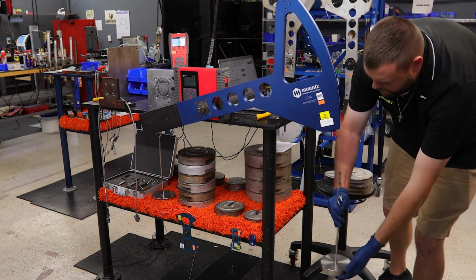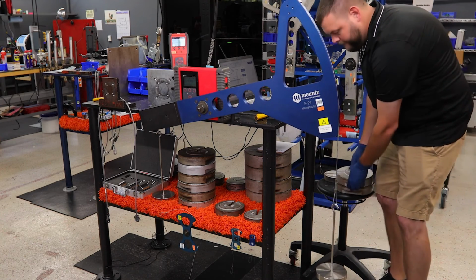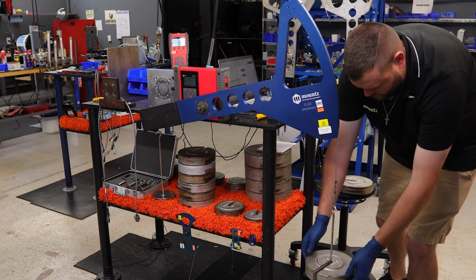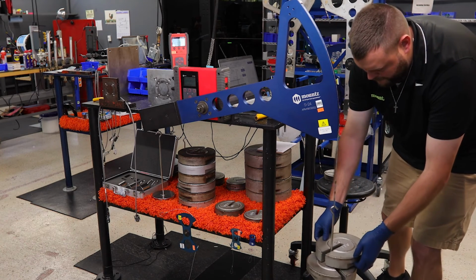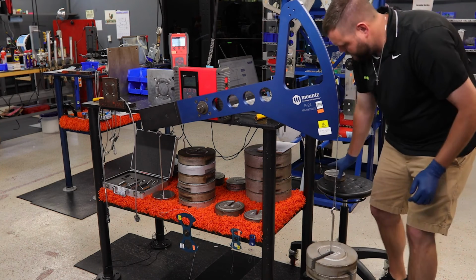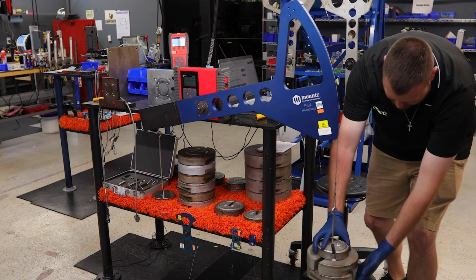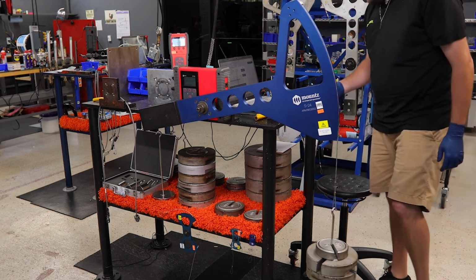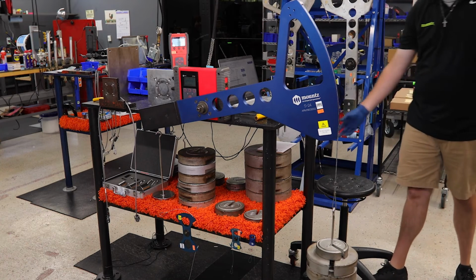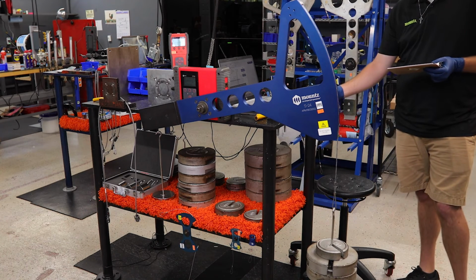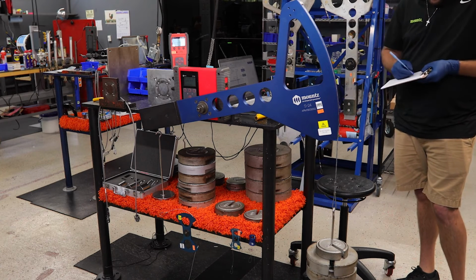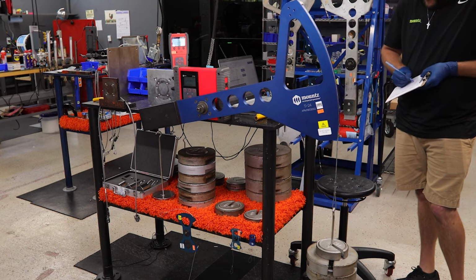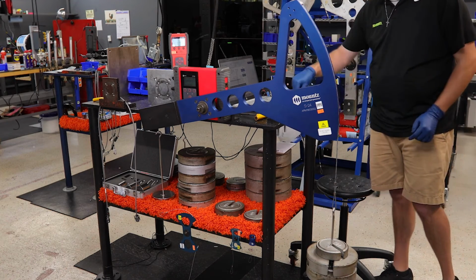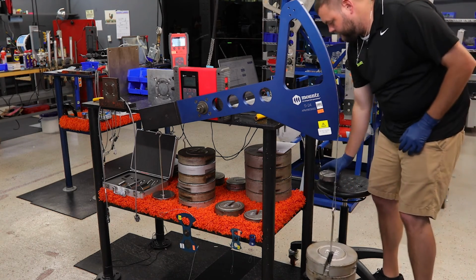And then this process is completed in the counterclockwise method, the same value or same readings at 10, 50, and 100. And then after that has been completed, the calibration data, as I mentioned, will go to the ARC2 chip where it will be stored there. And then the process will be validated to make sure that the sensor is reading correctly with that. And then at that point, the calibration has been completed. So the process itself is not too terribly difficult. There is just a number of things that need to be managed within the process.